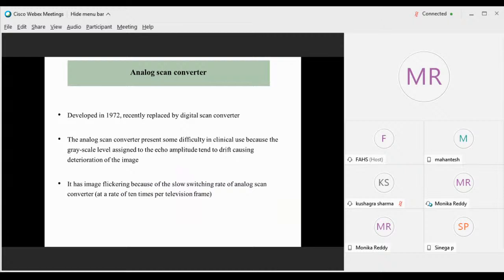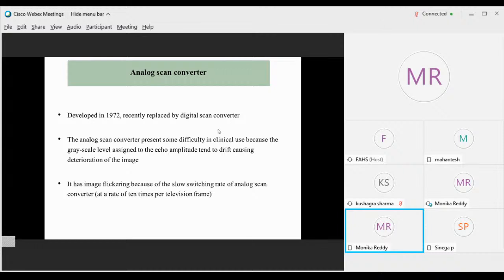The analog scan converter presents some difficulty in clinical use because the grayscale level assigned to the echo amplitude tends to drift, causing deterioration of the image quality. That's why we are not using the analog scan converter. It also has image flickering, like when we are sweeping the transducer, and the flickering is greater with the analog scan converter. It is not fast enough to switch the rate of analog scans.